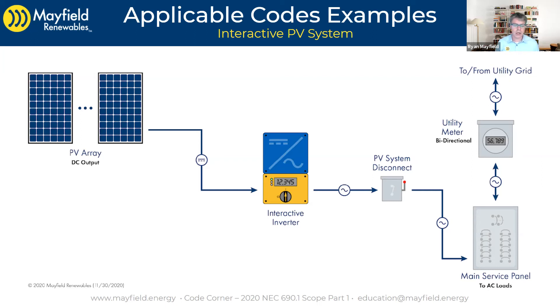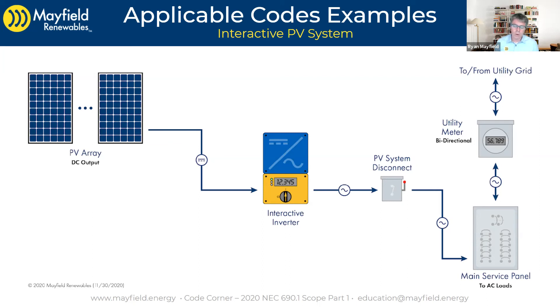So this was a pretty big change when you really think about it. One of the places where this really comes into play is when we start talking about rapid shutdown and what conductors have to be controlled — you're going to need to control your PV system conductors. Having this PV system disconnect and this finite point that says 'I am disconnecting my PV system here, everything else is not part of the PV system' really helps add some clarity to that. We'll talk about that when we cover the rapid shutdown requirements — helping set that stage is the reason I wanted to go through this image.